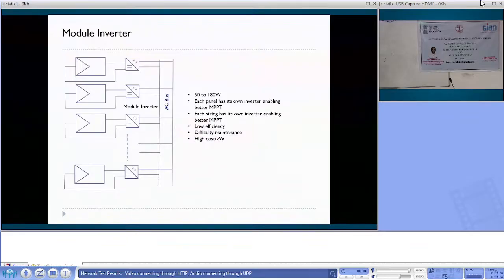For a string, this is the curve you want, the total string PV curve, where the voltage gets added. No, we don't generate that kind of PV curve. We don't require that PV curve. We just sense the voltage and the current and give that value to the MPPT algorithm, which will sense the initial P1 and P2, V1 and V2. So it is changing from 1 to 2.